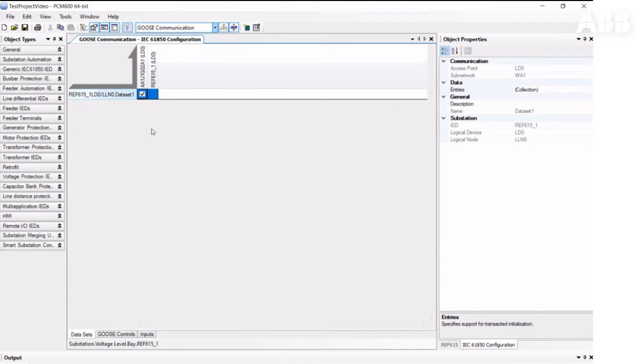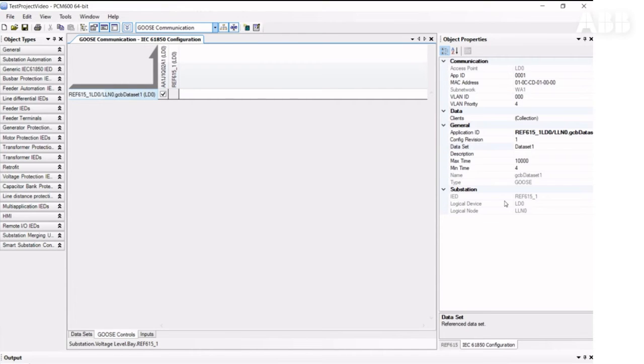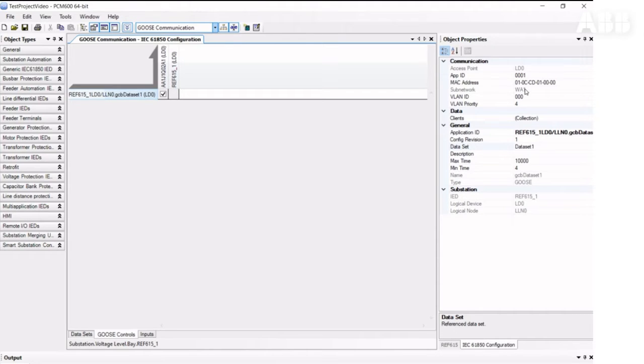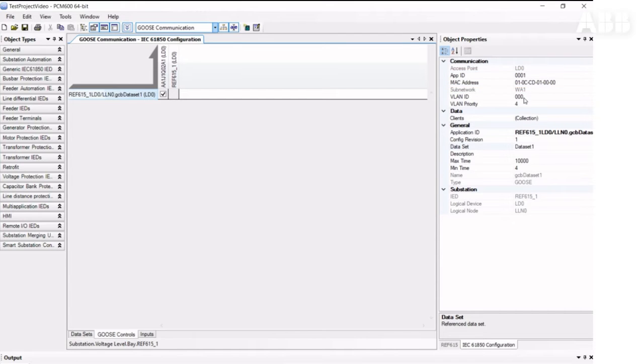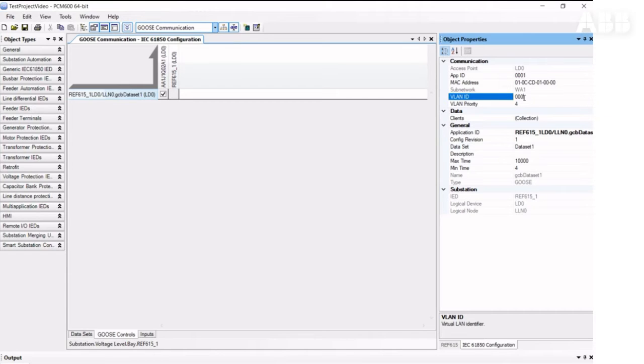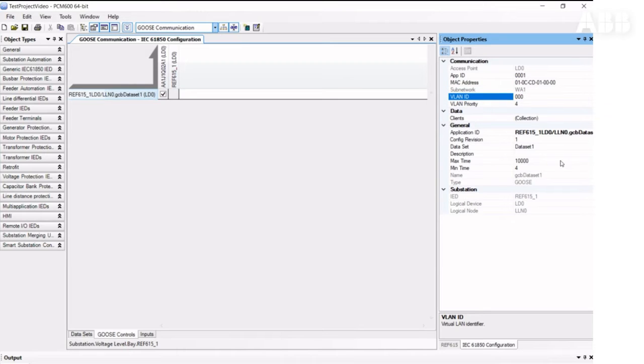Then here, we will look at what kinds of parameters we can change. When you create everything in PCM600, it automatically creates a unique APP ID and MAC address for every GOOSE control block, as is required by the standard. But if you have different requirements, you can change the APP ID and MAC address. If you use a VLAN configuration in your project, you can change it here.